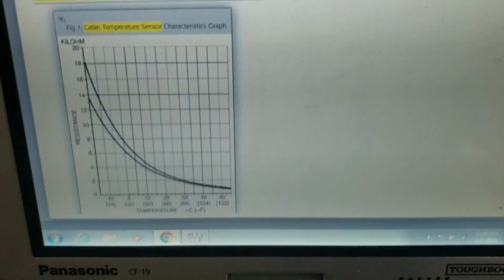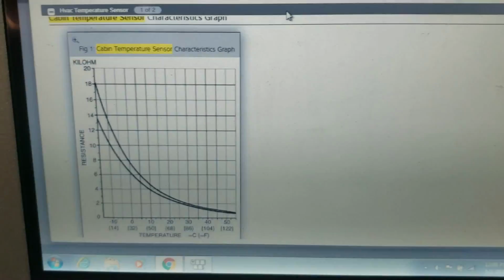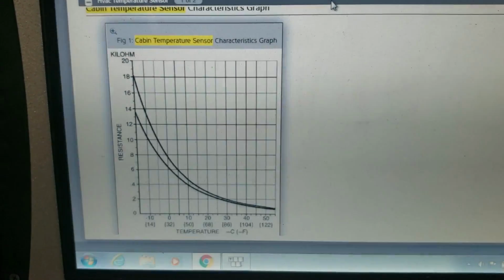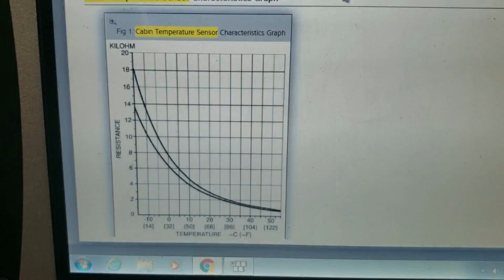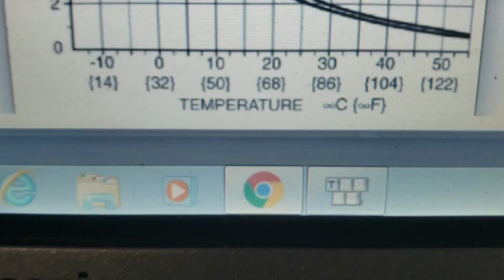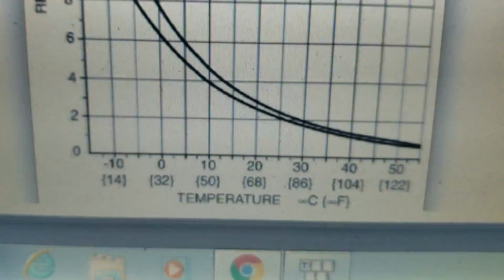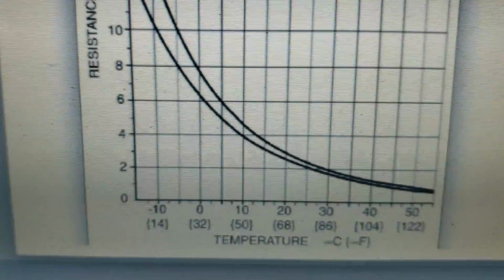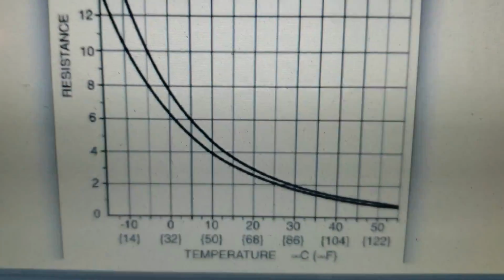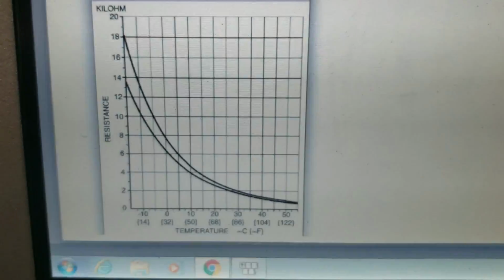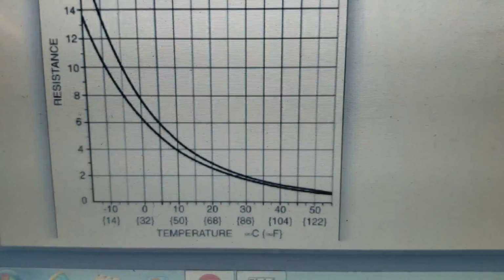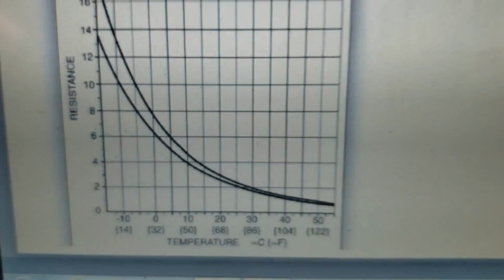So luckily for us, Mitchell in this case had some service information with regard to testing that evap temp sensor. You can see right here that's 50 degrees Fahrenheit, and if you follow that over to your left is the resistance of that sensor. It looks like it's about 4, that's kilo ohm, so about 4,000 ohms should be about 50 degrees.